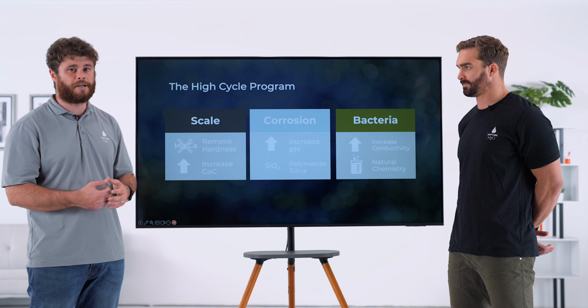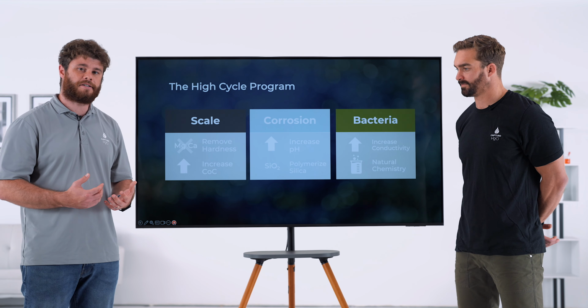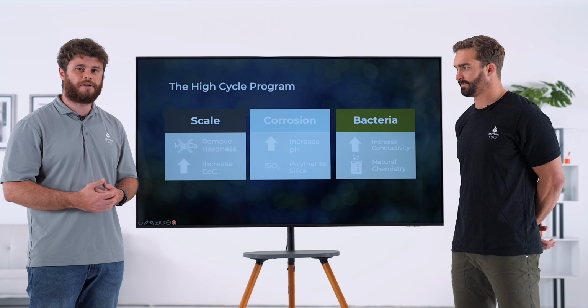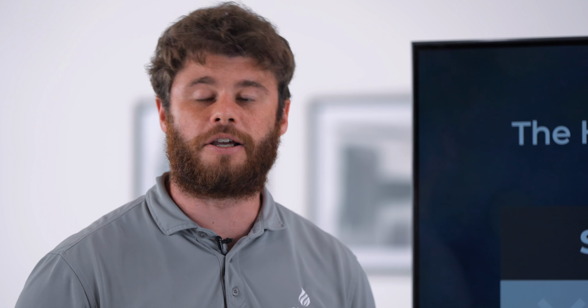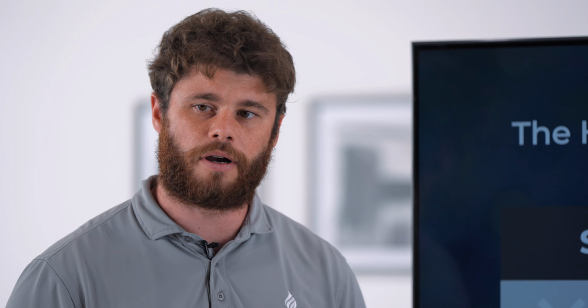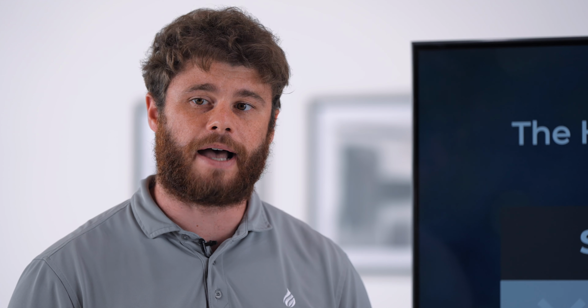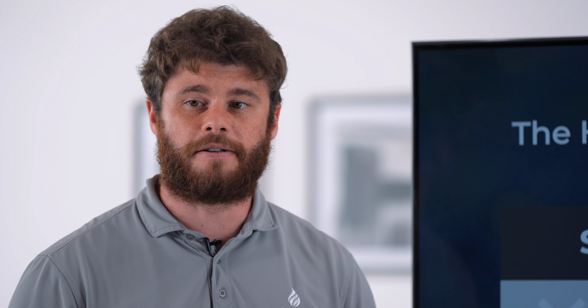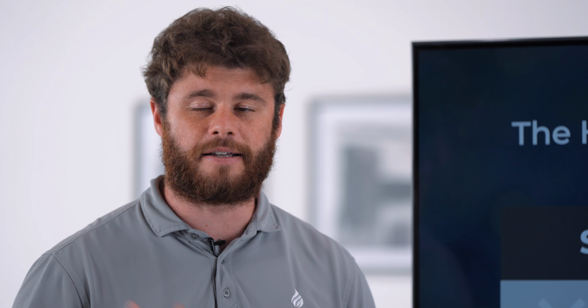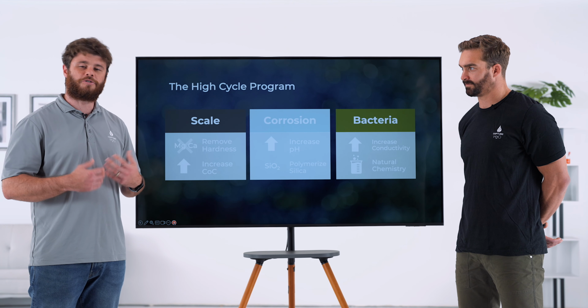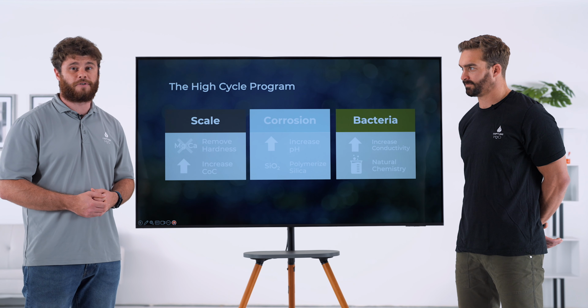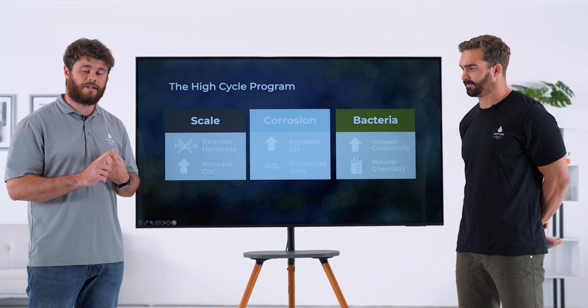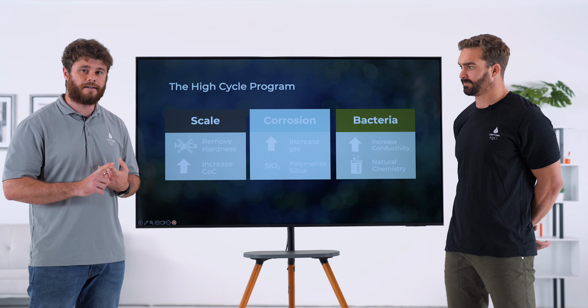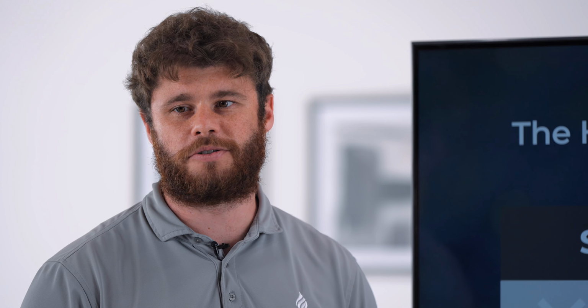Lastly, step three, bacteria. Very similar to how we control for corrosion, when we increase our pH and increase our conductivity in the cooling tower, that creates what's known as a biostatic environment. And it's an environment that bacteria cannot exist or procreate within, using two principles that have been around for thousands of years. First being high conductivity. It's what we see in the Dead Sea. High osmotic pressure impacts life forms' ability to survive.